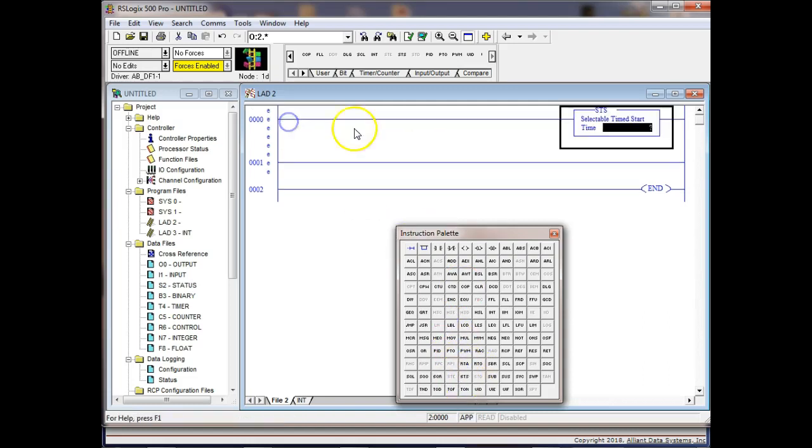We also have another thing available where I can come out here and put STS. Now, STS is an instruction, and it's an output instruction. And we just come up here and we set a time. So I can change the time between the interrupts, right? You understand? I can do that through software, but I can't set up the STI through Easy. We could, but it would be a lot harder to do.